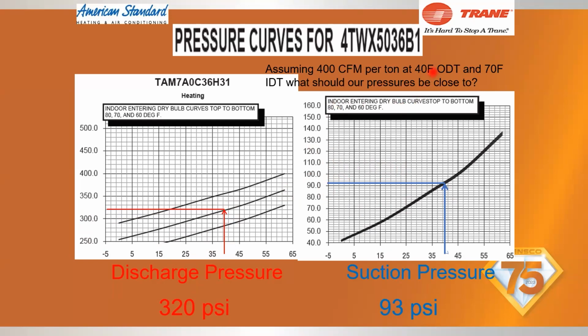So with a 40 degrees outdoor temperature, a properly charged system would be about 320 PSI over 93. So again, this is to get you close, and this is to get you feeling good about the charge. And of course, this is after 20 minutes of runtime.